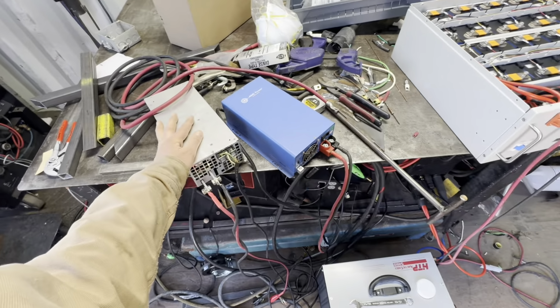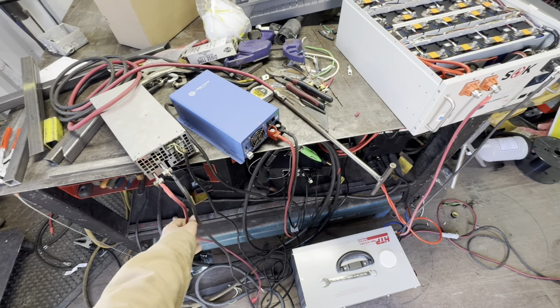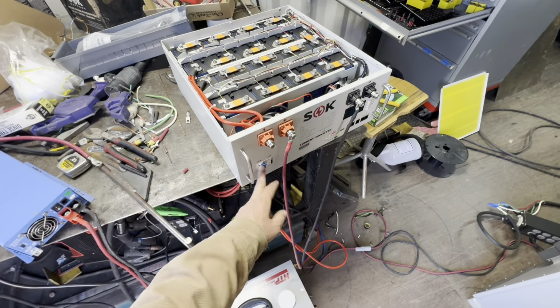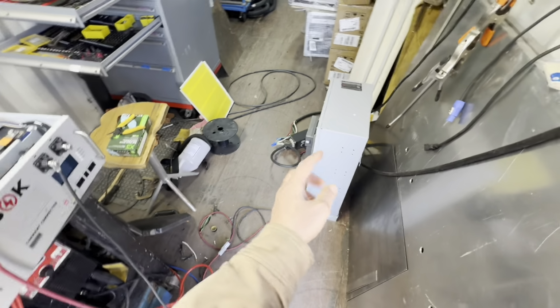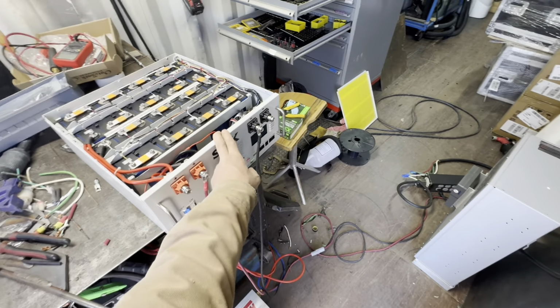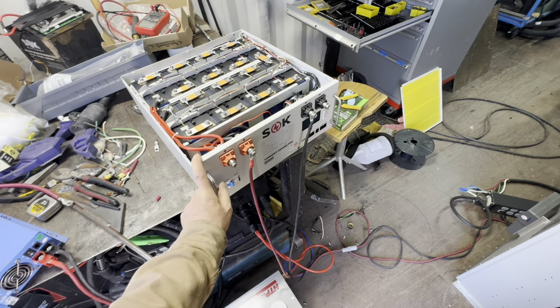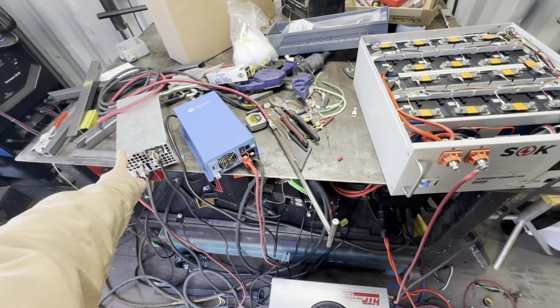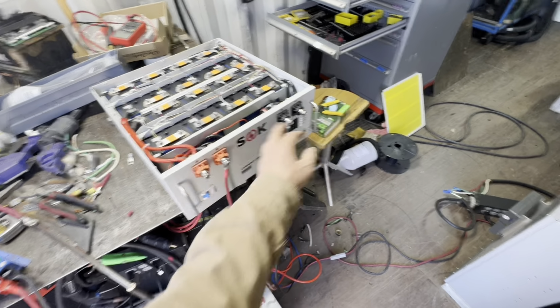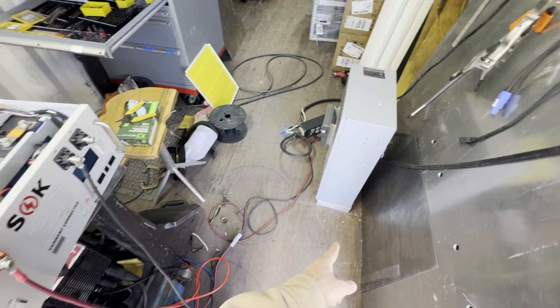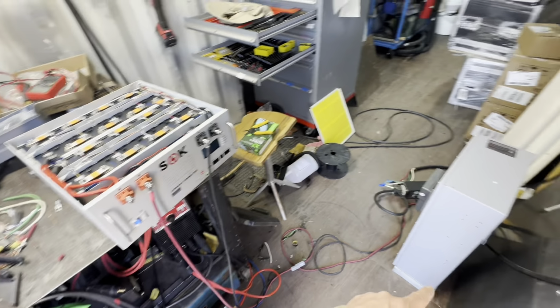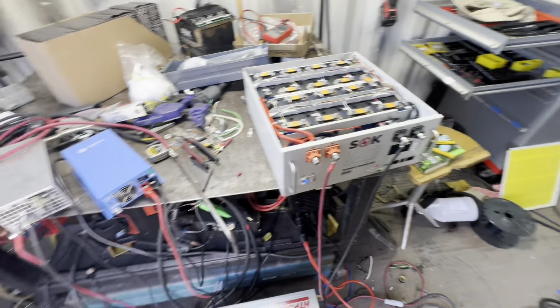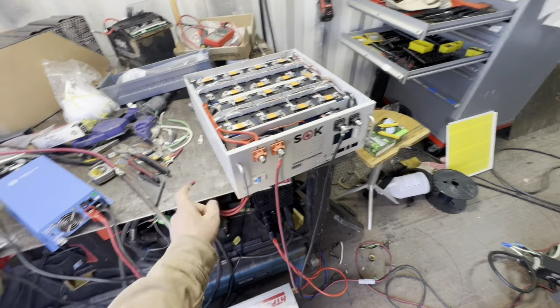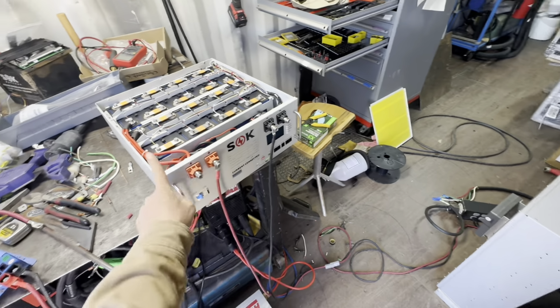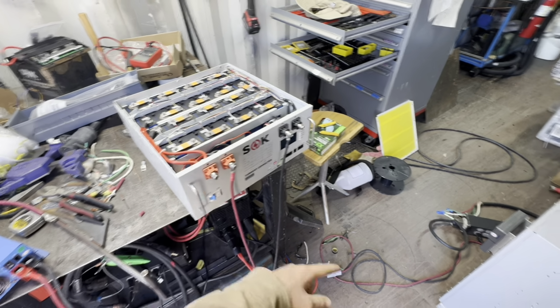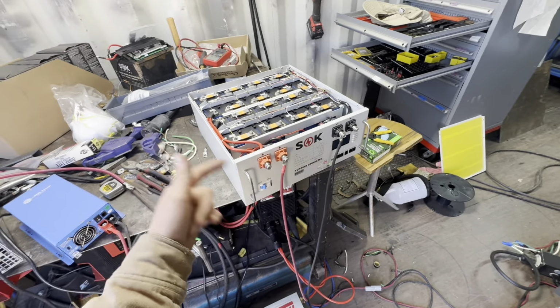The other thing I did with this today was — before I turned this circuit breaker on — what happens with this inverter is the big capacitors in it will make this think it's a short circuit, so it will shut off. What I do is turn off the breaker, connect the 48 volt power supply to these terminals, or any terminals, and then start the inverter. Once the inverter is running with no load on it, I turn the circuit breaker on and take away the power supply. That way, the power supply charges those capacitors before I bring the battery into the circuit, which stops the battery from alarming for overcurrent or short circuit.